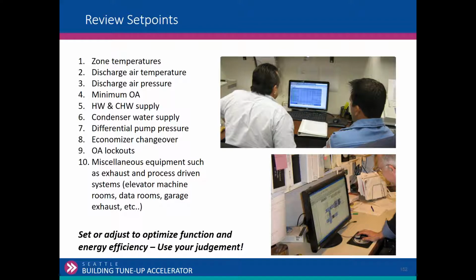to try to minimize that simultaneous heating and cooling. Exhaust and process driven systems, so data rooms, garage exhaust. If you've got a building with underground parking, then you're probably going to have, if it's a newer building, some sort of carbon monoxide control of the exhaust, or now under the newer codes, it's dual gas, nitrogen dioxide and carbon monoxide. So you can test those and see if those are running correctly.